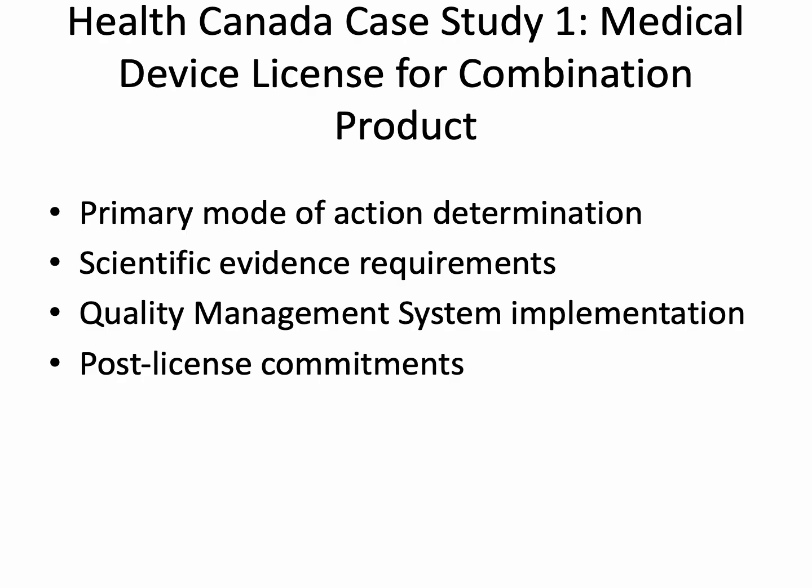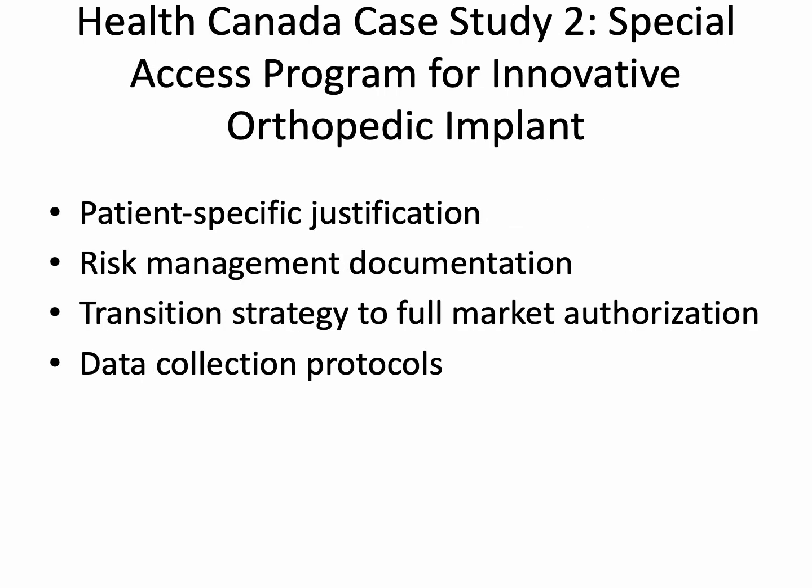A company utilized Health Canada's Special Access Program, SAP, to provide a novel orthopedic implant for patients with unique clinical needs. Each case required detailed patient-specific justification, outlining unmet medical need and risk-benefit assessment. Risk management documentation included design verification, failure mode analysis, and mitigation strategies.